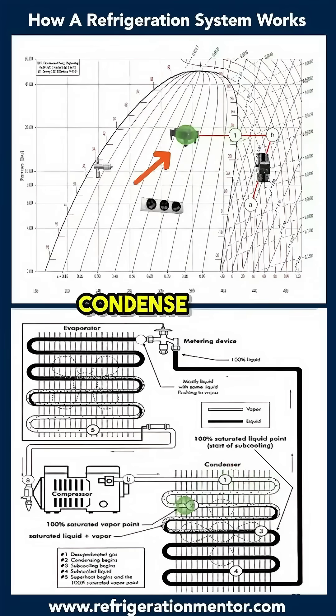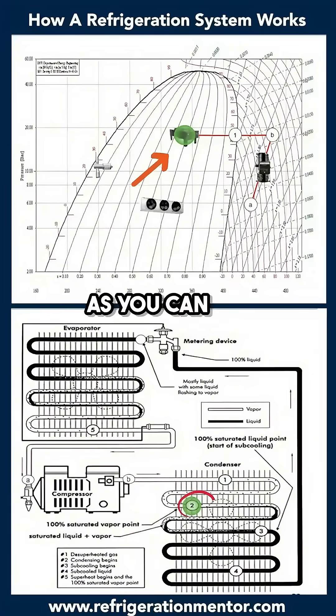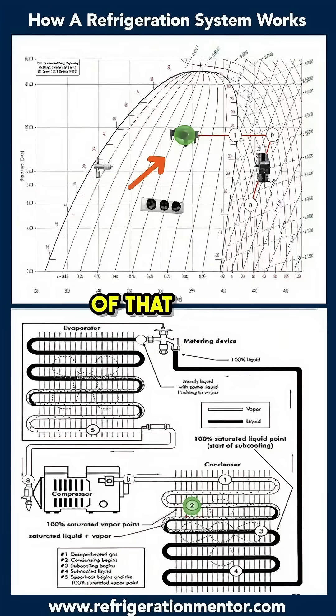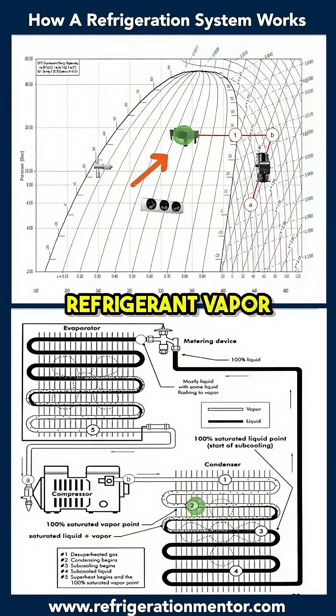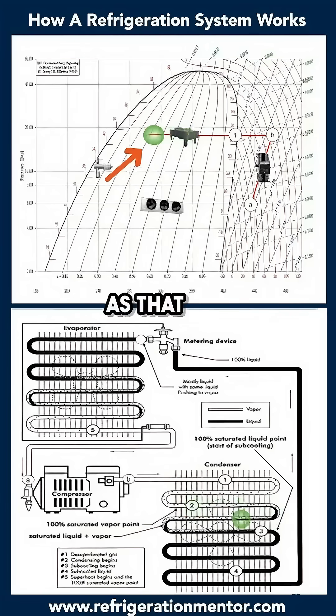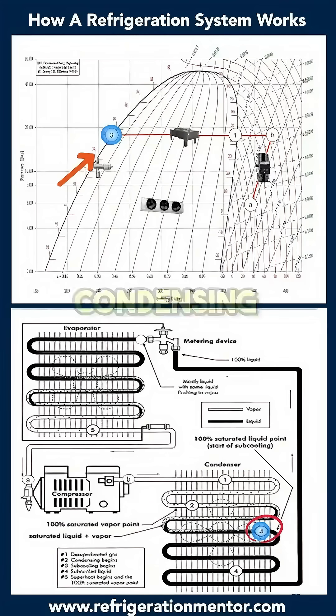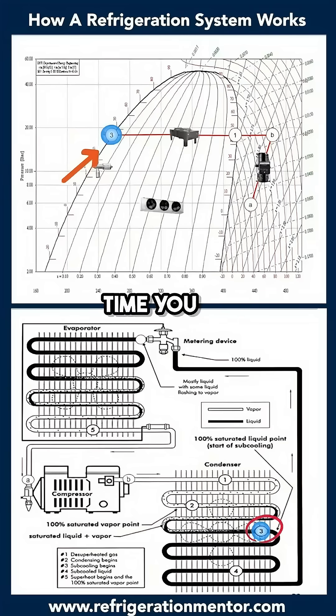When you hit your dew point, this is when you start to condense. Inside the enthalpy diagram, as you can see at point 2, that's where the condensing starts — you're starting to drop liquid out of the refrigerant vapor. As that fan blows across the coil rejecting the heat, you start to get more and more condensing happening.